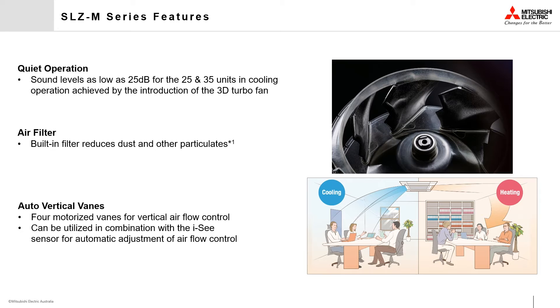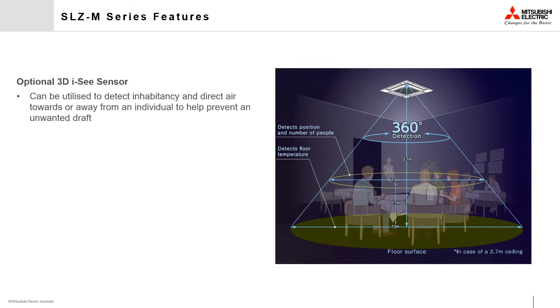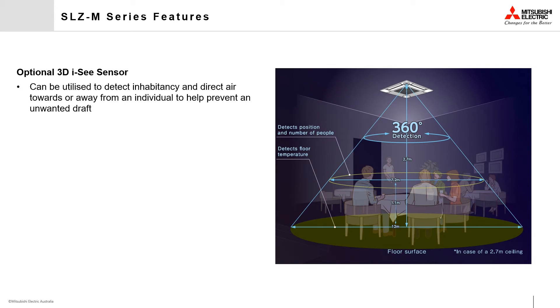Additionally, the vanes can be controlled by the optional 3D i-See sensor to automate some of these functions. The optional 3D i-See sensor, when activated, analyzes the temperature of the room by rotating clockwise and counterclockwise every three minutes. When linked to the four vertical airflow vanes, this sensor can be used to automatically direct air towards or away from occupants it detects.